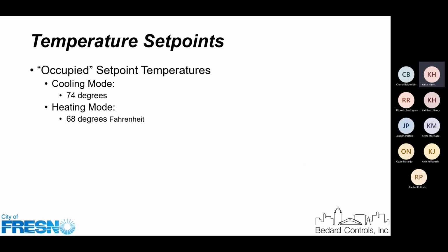Now, I bring that up because set points are something that were placed into the project so that it could model the energy savings that would be achieved. But set points are a variable depending on how that space is being used and the importance of that space to keep its occupants as comfortable as possible. So 74 and 68 are what's in the model. That predicts the energy savings that could be available. That's what paid for the thermostats to be installed. That's what paid for the new equipment to be installed at various sites.